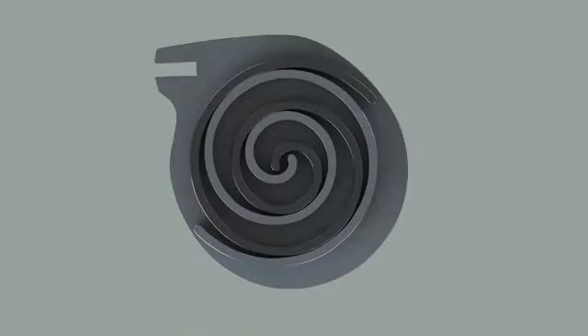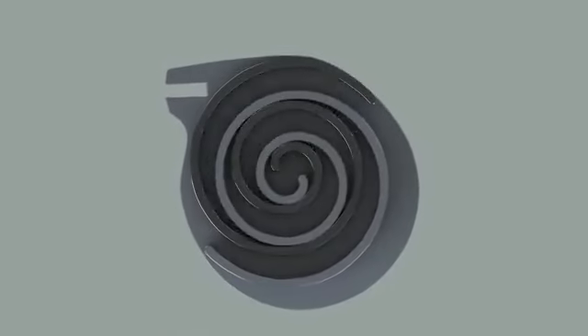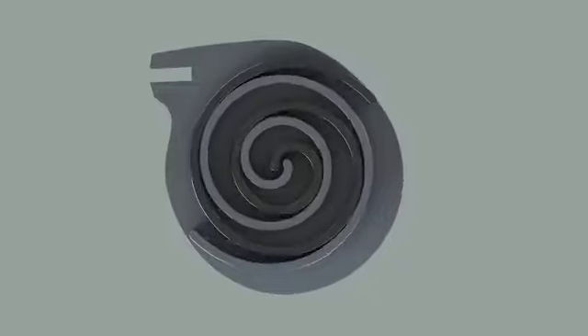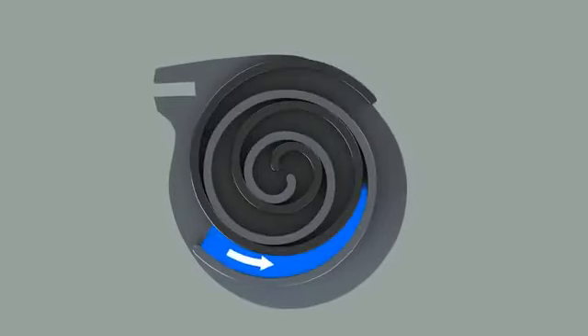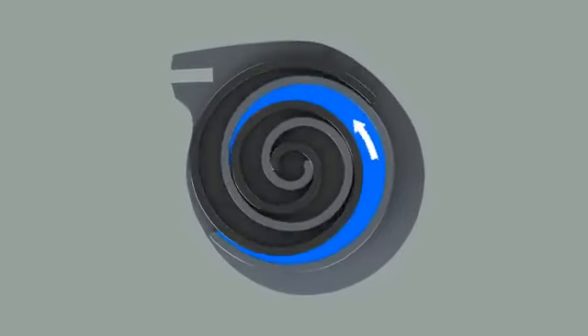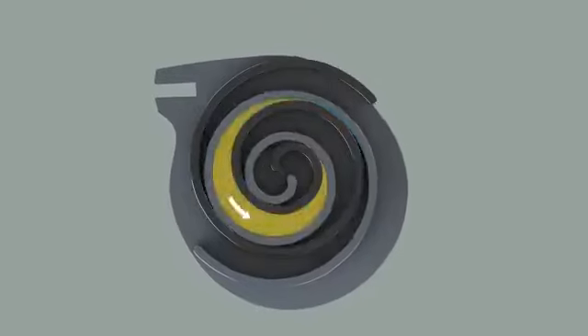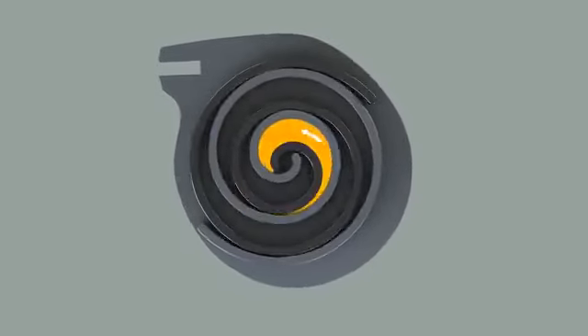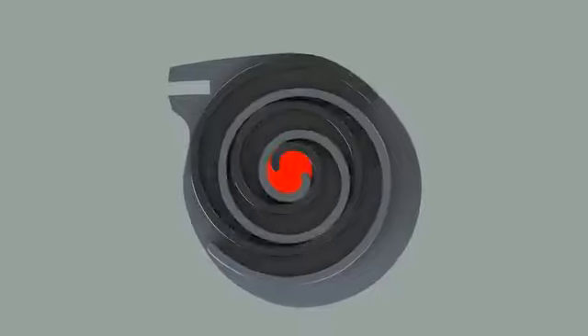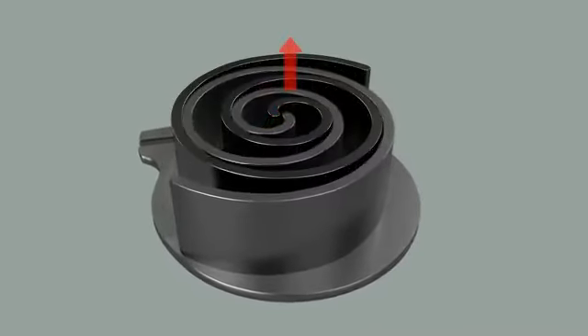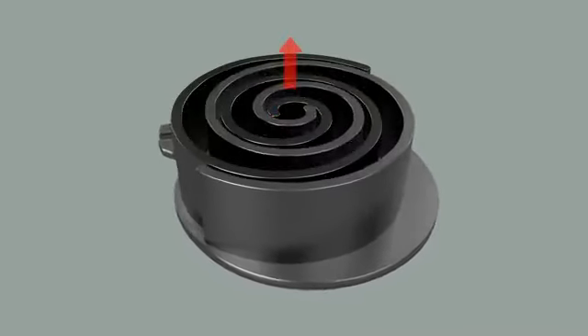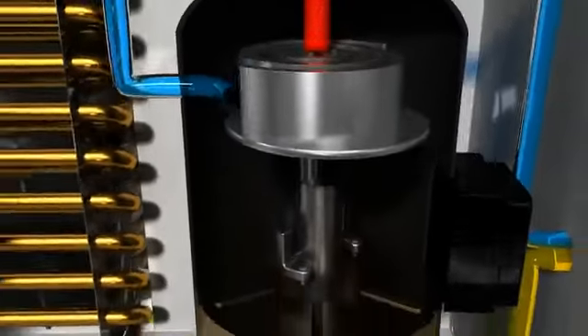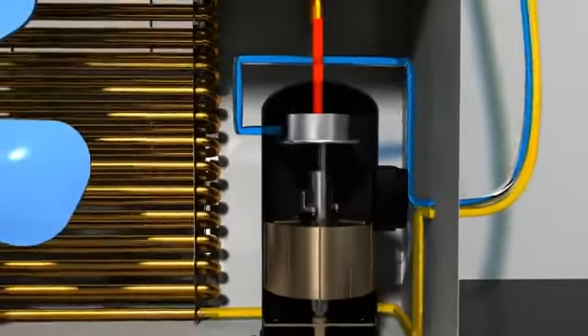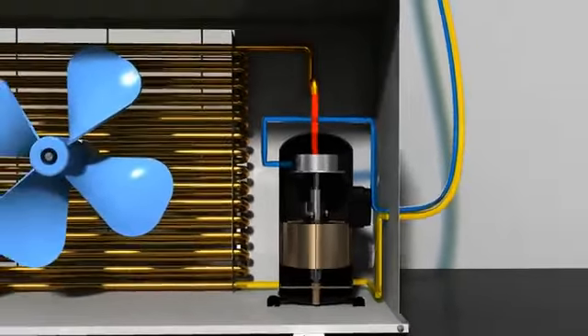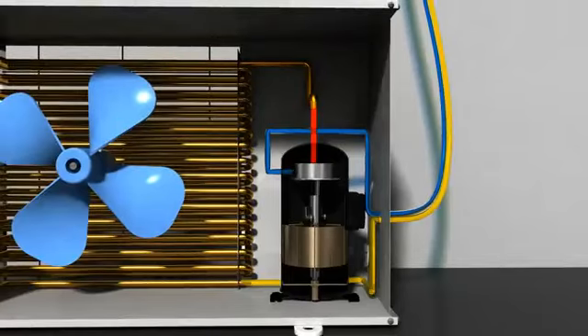In a scroll compressor, there are two scrolls, of which one is fixed and the other rolls constantly. As more air coming through the entrance gets inside the scroll, space becomes crowded. As there is less space now, gas becomes more compressed and is discharged from the middle of the scroll in a compressed state. The reason for using such type of compressor is the efficiency of space utilization. This type of compressor allows the machinery to become smaller in size and reduces noise as well as vibration.